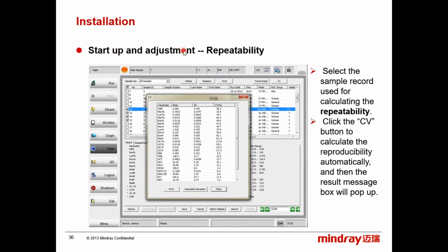Okay, then you do the repeatability test. This is also very important, the repeatability test. Here, what do we do for the repeatability test? We do 11 repetitions and we omit the first one. Okay, so we start from N2 to 11, okay, to get 10. And then we'll see the specifications. All right, this one also I will explain in detail. For the repetition, of course, we take into consideration the CVs except for the differentiation. For the diff, we take the SD instead of the CV. Okay.